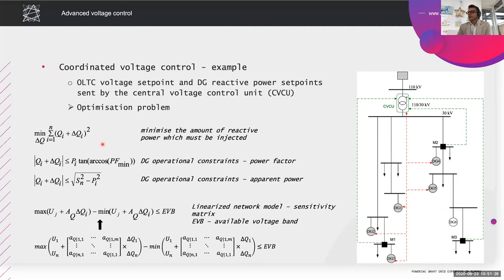So you are having multiple controllable elements. Let's say you have a transformer with a tap changer, which is able to control the voltage. You have distributed generators, which are able to control the voltage by means of reactive power. And of course, what you want to do is control the voltage in your network with minimum injection of reactive power. So you would like to inject the minimum amount of reactive power which is needed to maintain the voltage within the required limits. So you set the optimization function, which minimizes the reactive power. Here in the second two rows, you set the operational limits. Clearly, each distributed generator has a limit regarding reactive power generation.